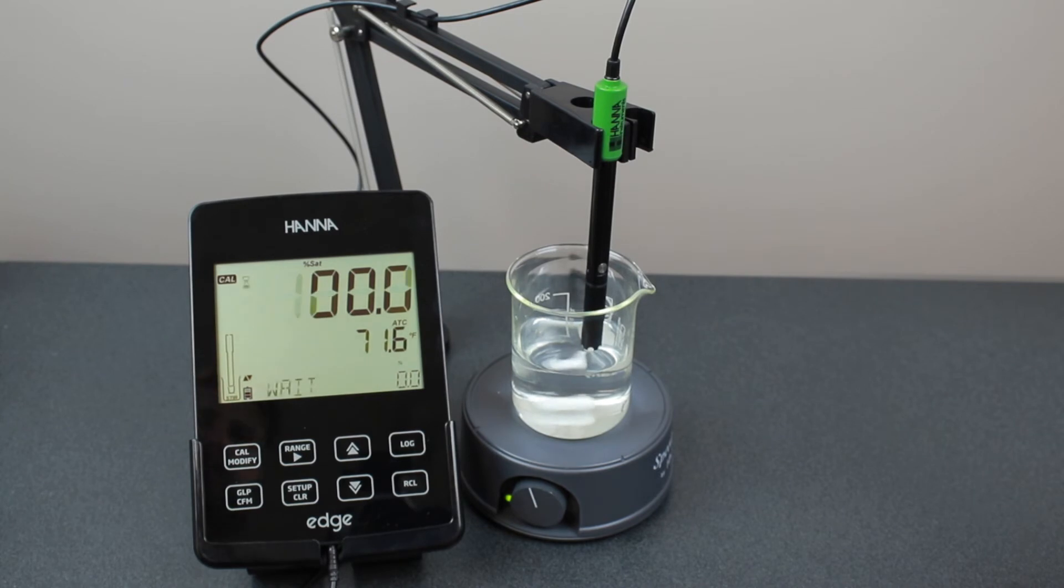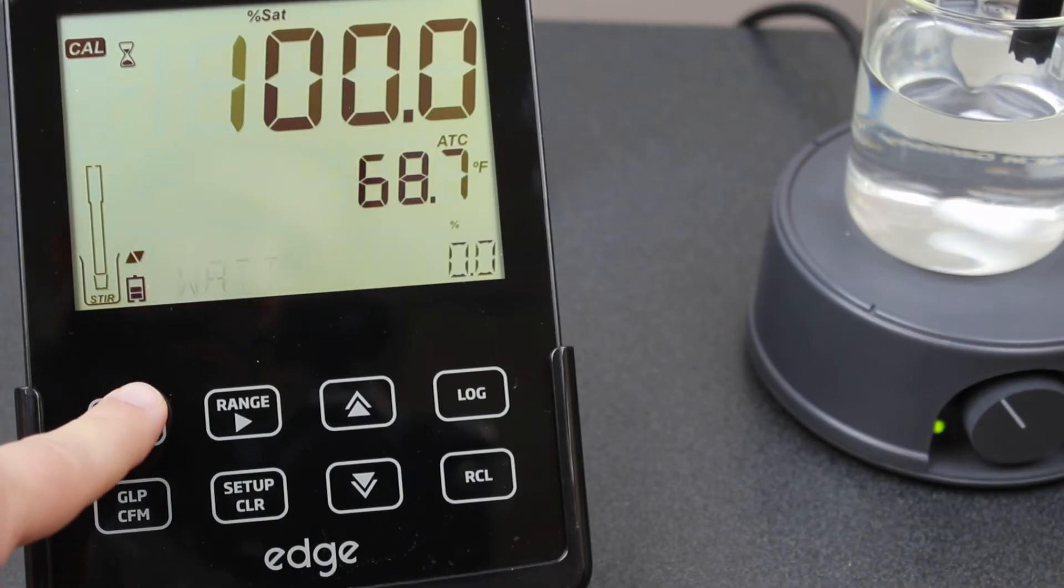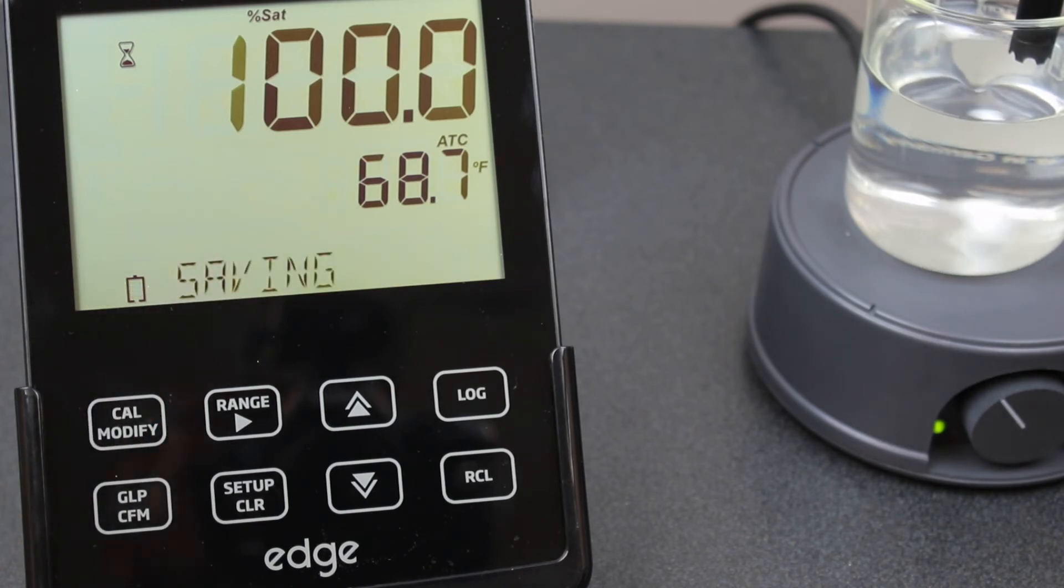The meter will display 'wait' and 0.0% will be displayed in the lower right corner. Press CAL to calibrate to one point and exit calibration. To continue with a 0% dissolved oxygen calibration...